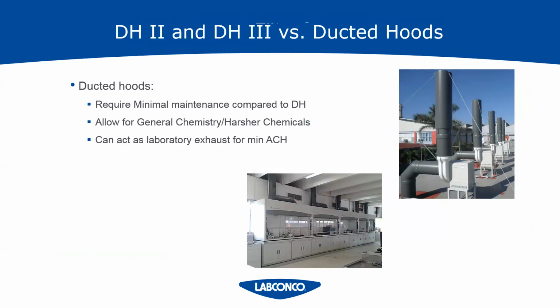So with a ductless hood, the user has to be trained to know what to do for different error codes. And there needs to be a backup plan in place for when the filters need to be changed on a ductless hood, because that hood is going to be down. You can't be using it when you're changing the filters out. And then you have to have the maintenance of the filter change out.